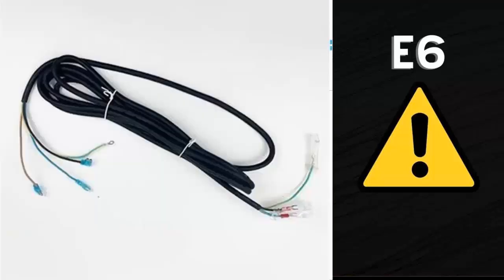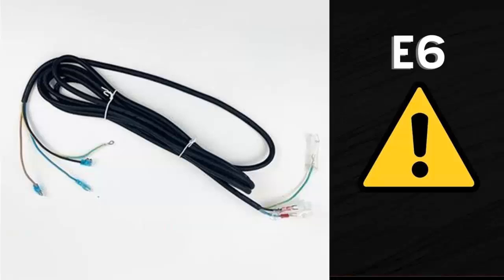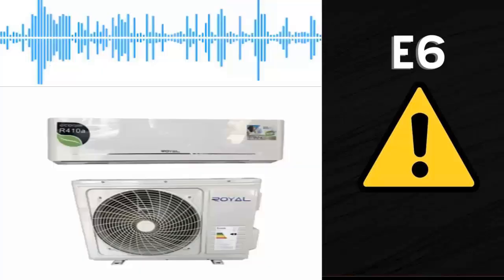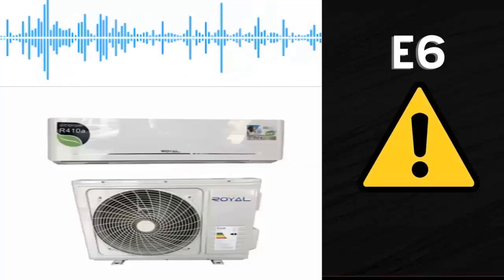Step 4: If the issue persists, you should install a temporary communication cable, only on the signal line — which is one of the three wires that the wiring connecting the internal and external units carries. This can be single-strand telephone wire without splices. If, during testing, you find that the equipment starts operating normally, it means you have a problem with the wiring and you should replace it entirely, making sure it has no splices.